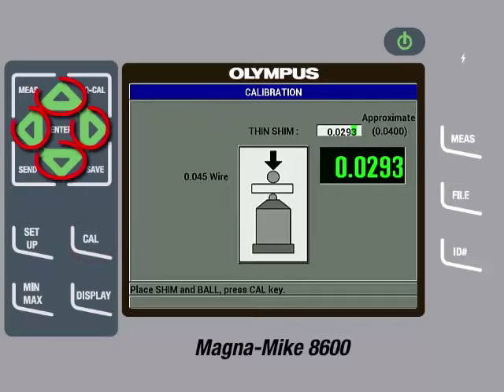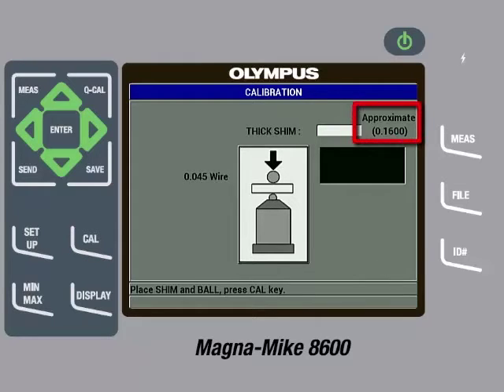Then use the arrow keys to input the precise thickness of the shim, which in this case is 0.0404 inches or 1.026 millimeters. Then press the cal key. We can then remove the wire and calibration standard. The gauge will then ask for a thick shim and call out an approximate thickness value for the thick shim to use. The thick shim called out for the wire target being used is 0.1600, or if you are using metric units, it would be 4.064.